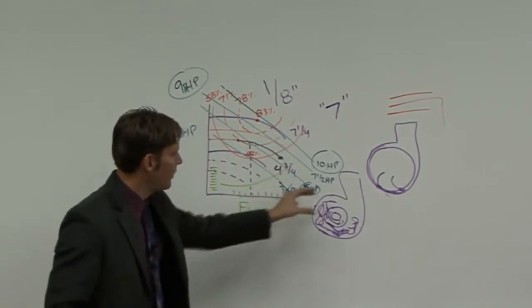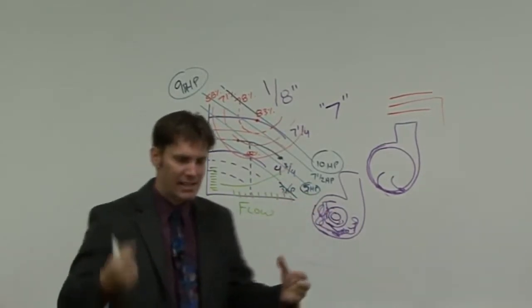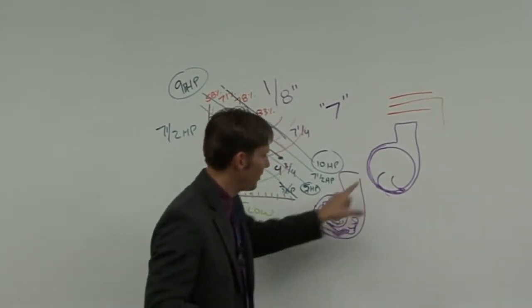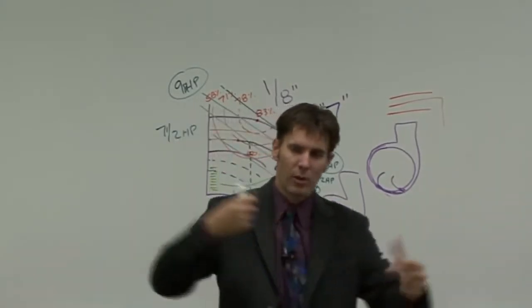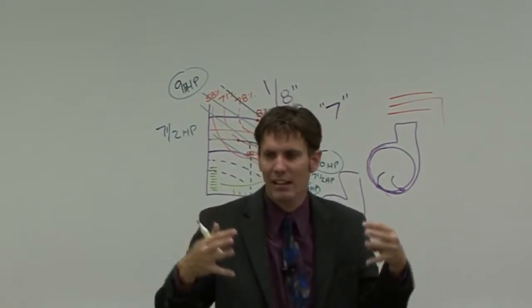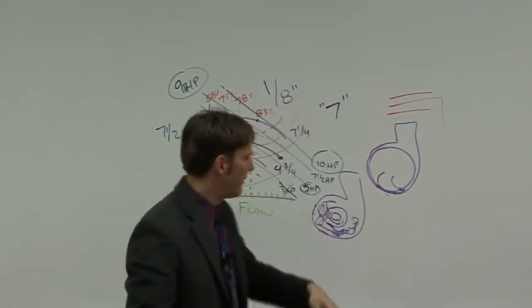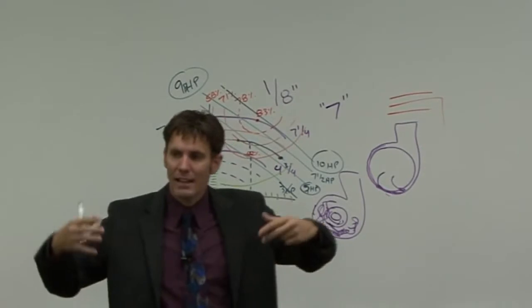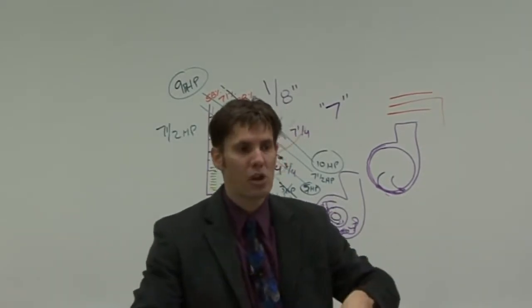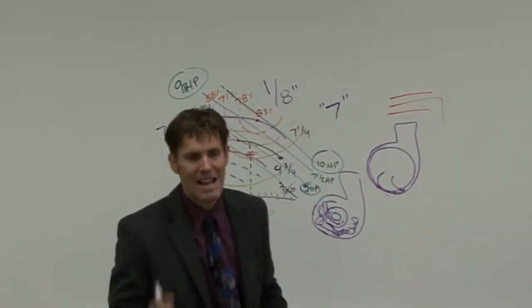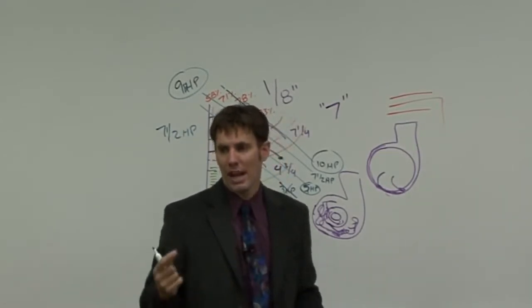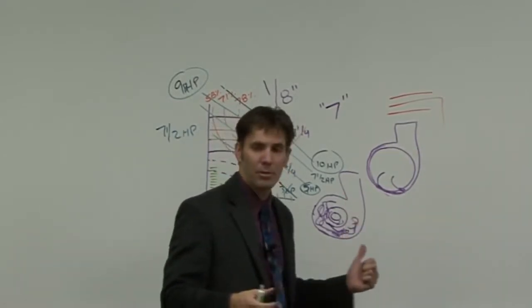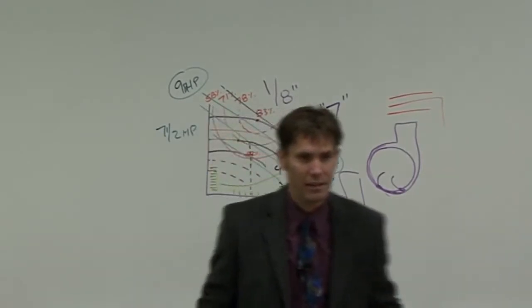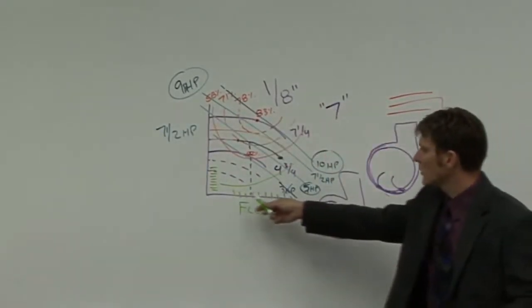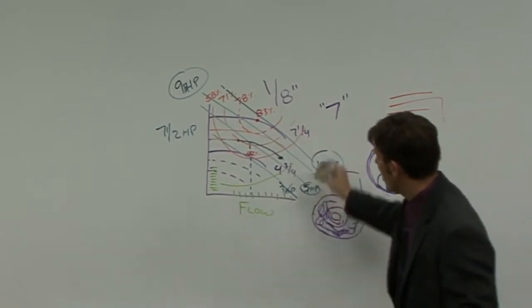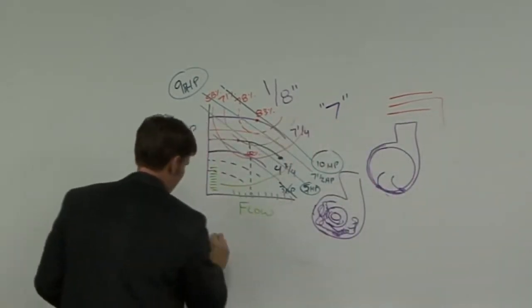The more flow I have moving through that pump, what's happening is the orifices in the pump don't change. As more and more flow is being forced through that orifice, it creates a larger vacuum. And as we create a vacuum at this point, we could create a large enough vacuum that we now start to boil the water. I have seen 85-degree cooling tower water boil and kill a pump because it's been cavitating.